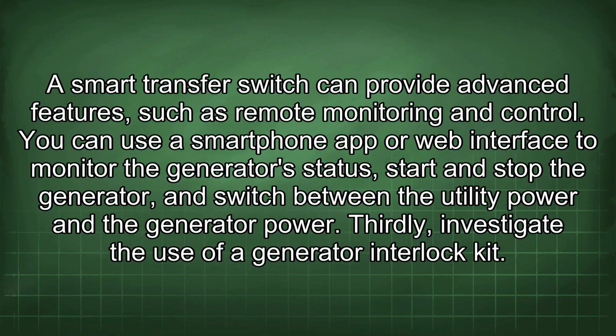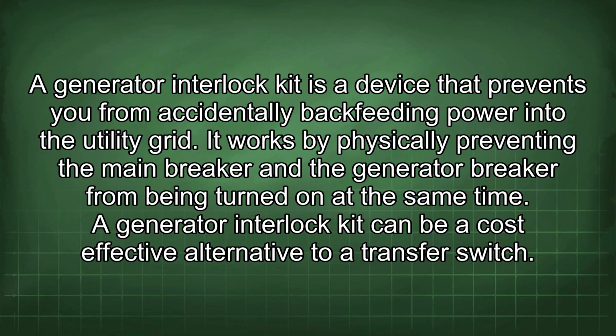Thirdly, investigate the use of a generator interlock kit. This device prevents you from accidentally backfeeding power into the utility grid by physically preventing the main breaker and the generator breaker from being turned on at the same time. A generator interlock kit can be a cost-effective alternative to a transfer switch.